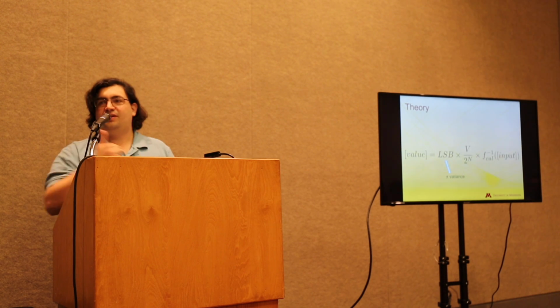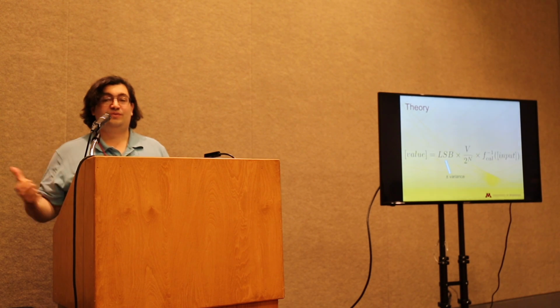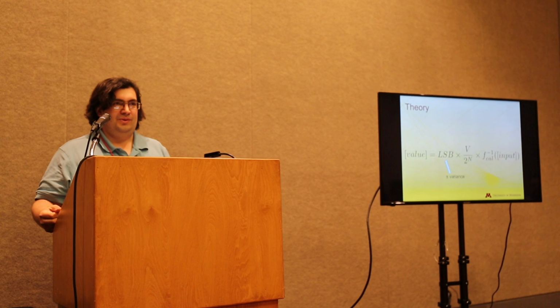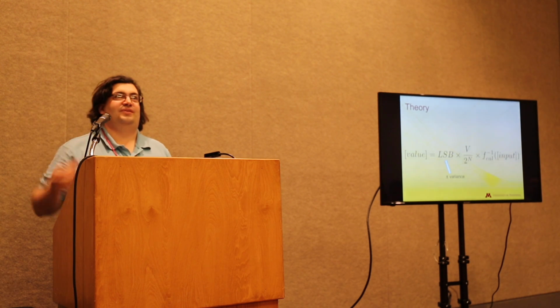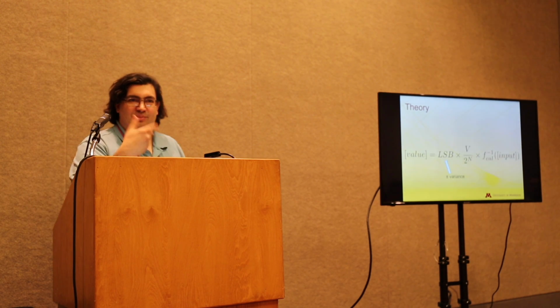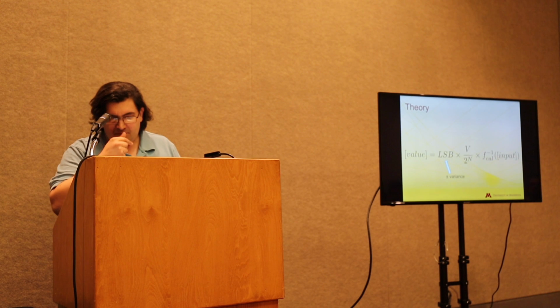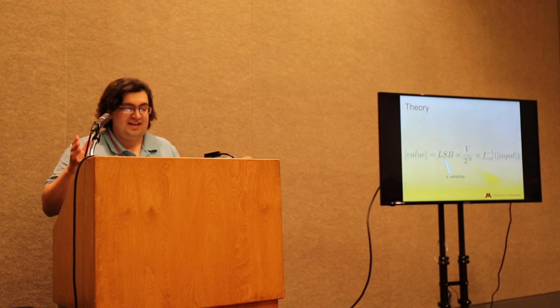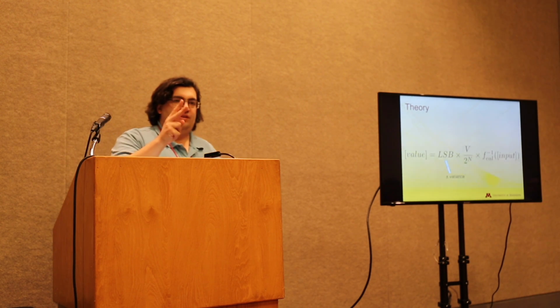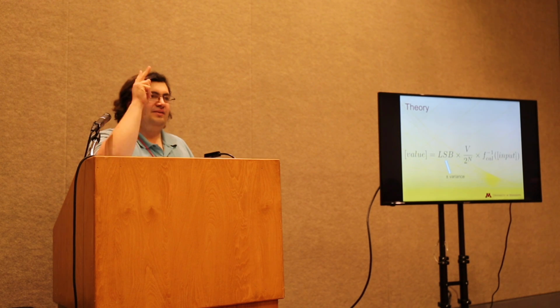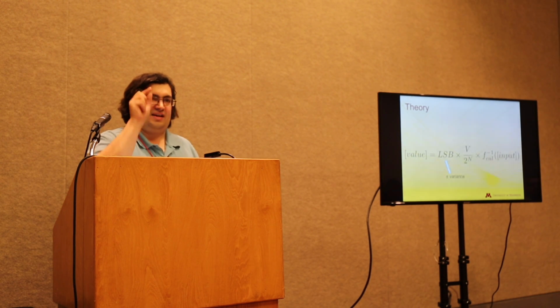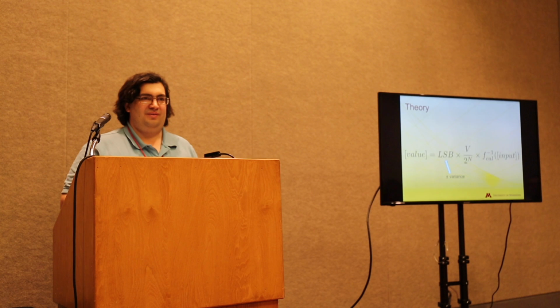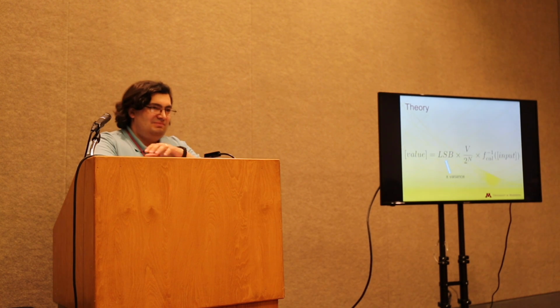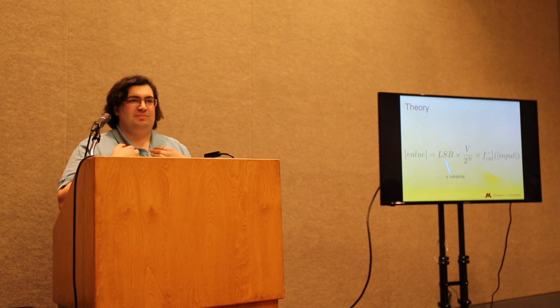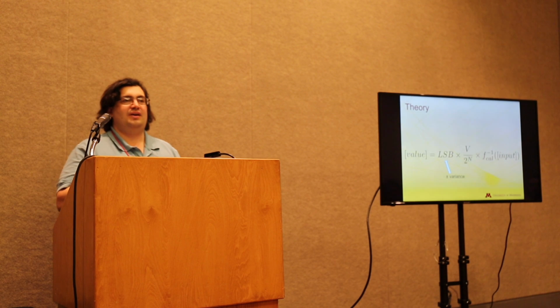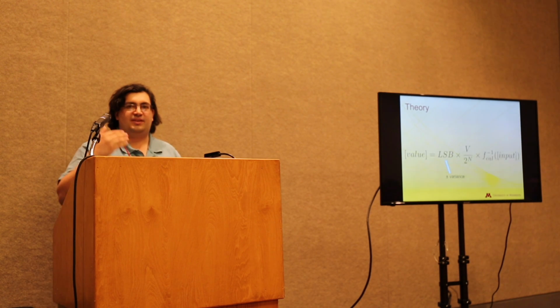Number one, you have converted back to the original units that are useful to people, like meters, or NTUs, nephelometric turbidity units, for how turbid water is, or relative humidity, temperature, any of these things. Number two, your measurement is not complete unless you have an uncertainty, a plus or minus after that number. If you don't have that, your number means nothing to me because I don't know what to compare it to. I don't know how uncertain I am about the measurement that has been made.